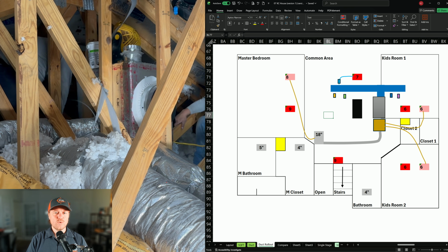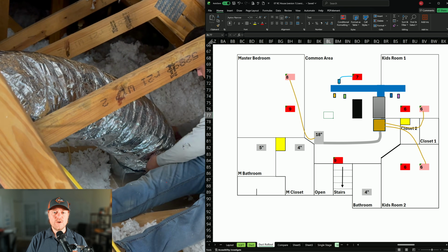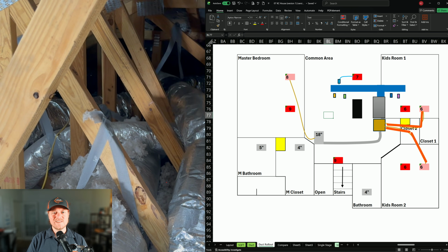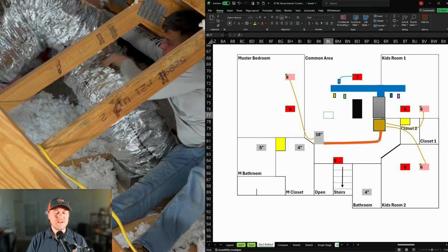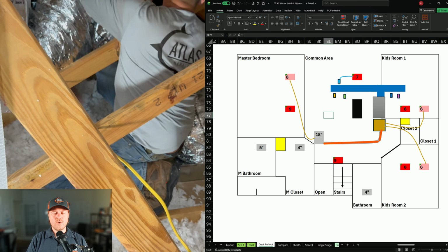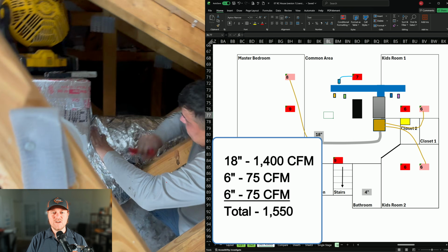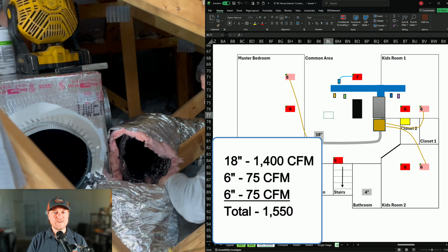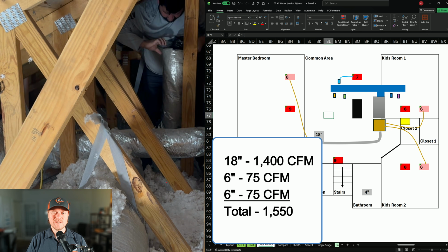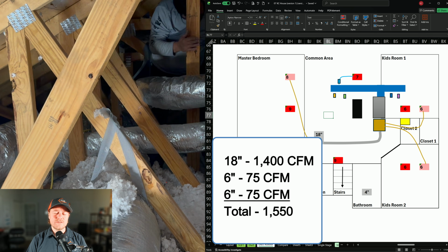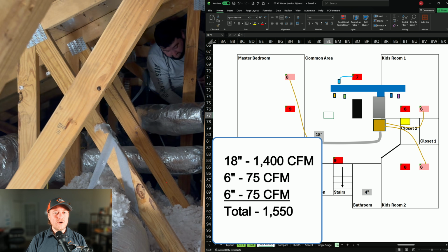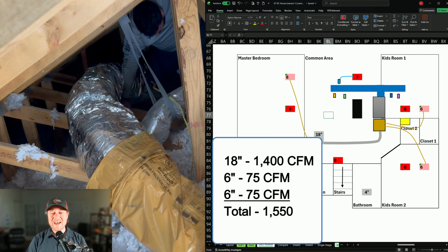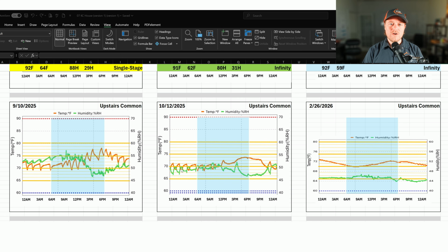We originally had 1400 CFM of return air, and for the new ductwork I can only factor in the 2 6-inch returns, because this 18-inch duct is only good for 1400 CFM. When we factor in the 2 6-inch returns, that increases the overall return air to 1550 CFM, pretty close to 1600 CFM. Now that we got our ductwork sized correctly for the system, what does this mean for temperature control? Did we actually fix our hot and cold spots? Well, let's take a look.